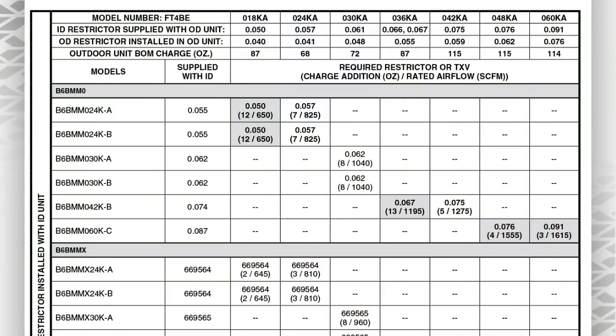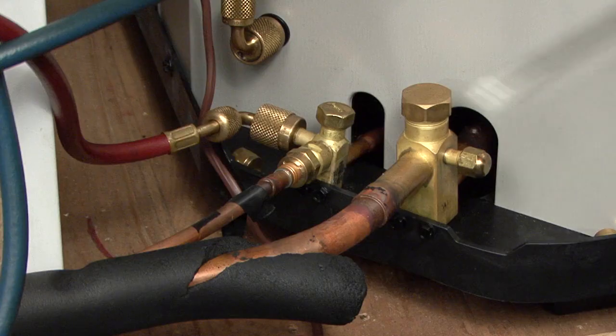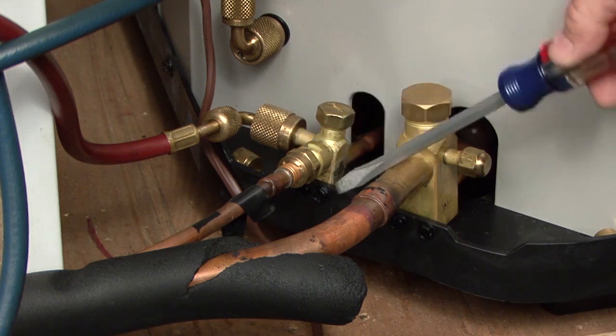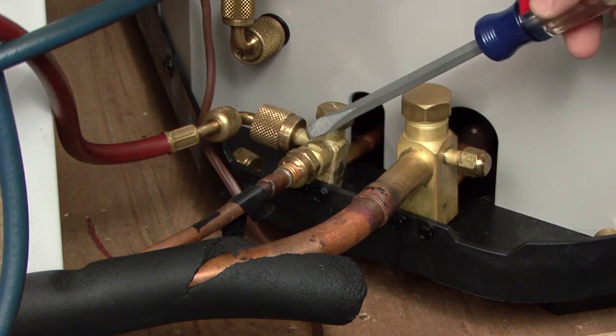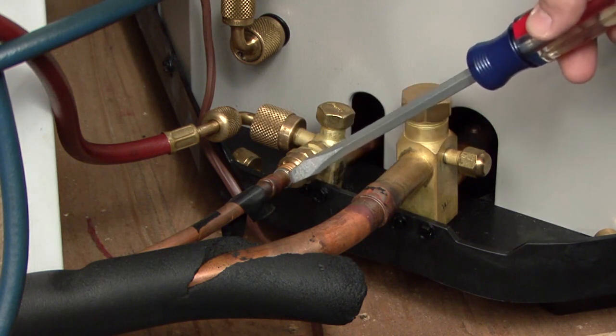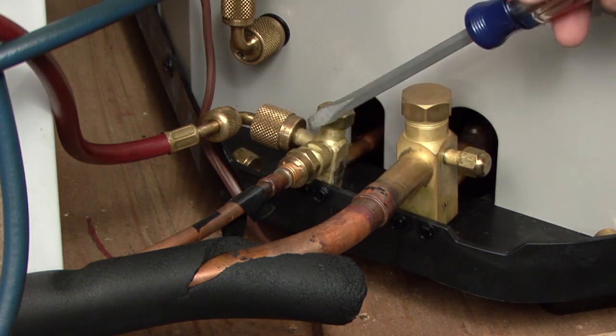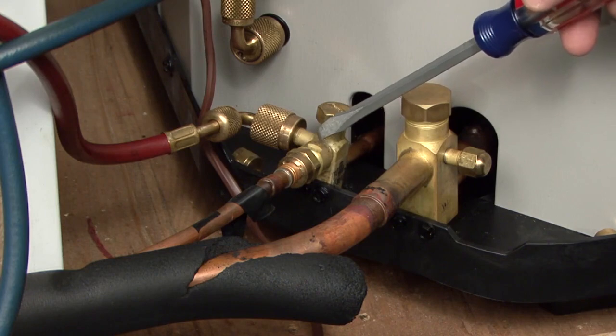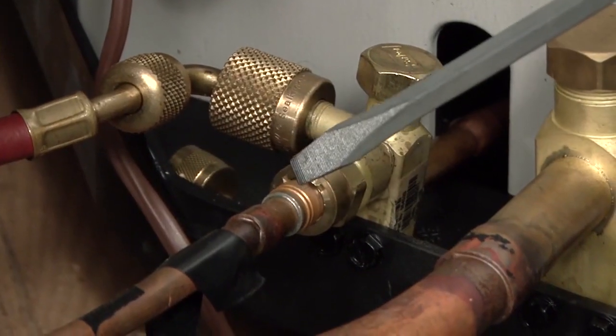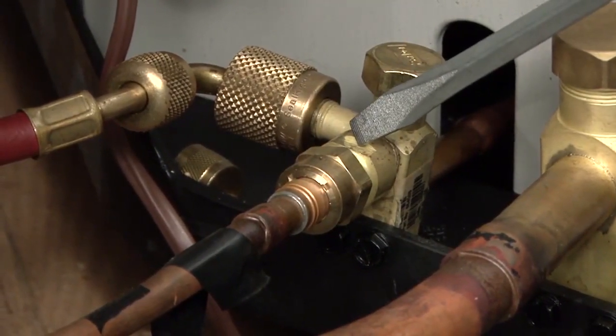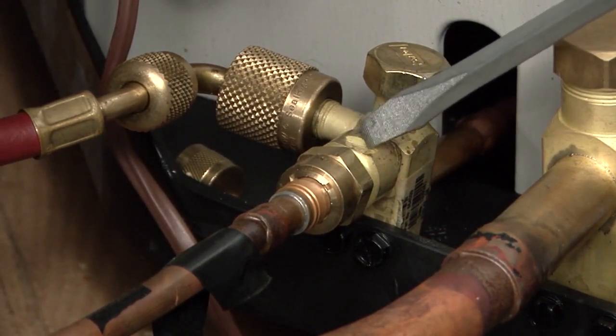So then the other things with the quick reference data sheet, hopefully you've put the appropriate orifice on the indoor unit, or you have the appropriate TXV on the indoor unit, depending on what that quick reference data sheet specified you needed in there. And out here, we need to make sure we've got the right orifice in the outdoor unit also. On the newer equipment now, we're putting the swivel connector out here, and the orifice actually is located right here in the liquid line service valve. Before you put this on here and actually solder your line set to it, we need to make sure we've got the appropriate outdoor orifice.